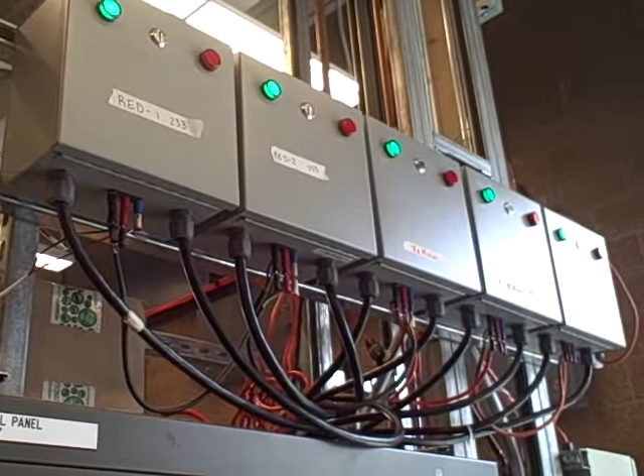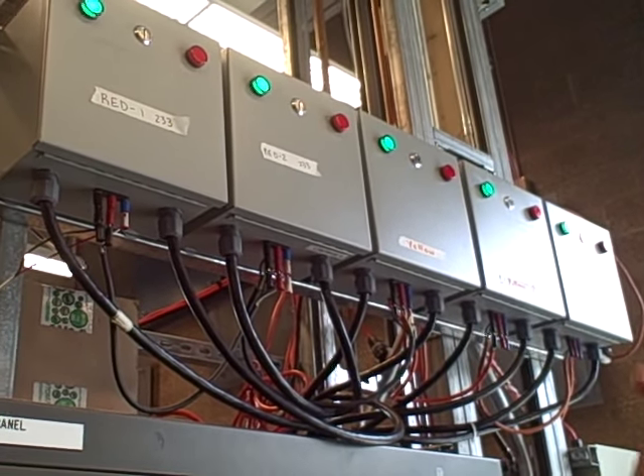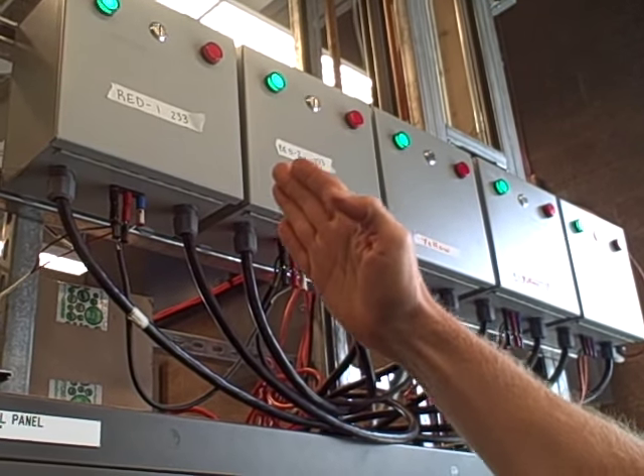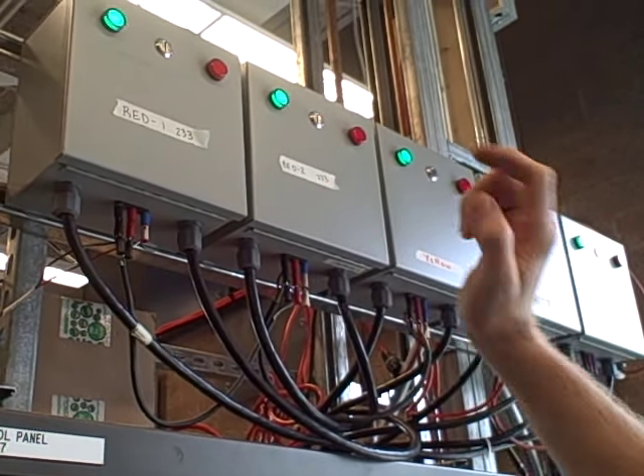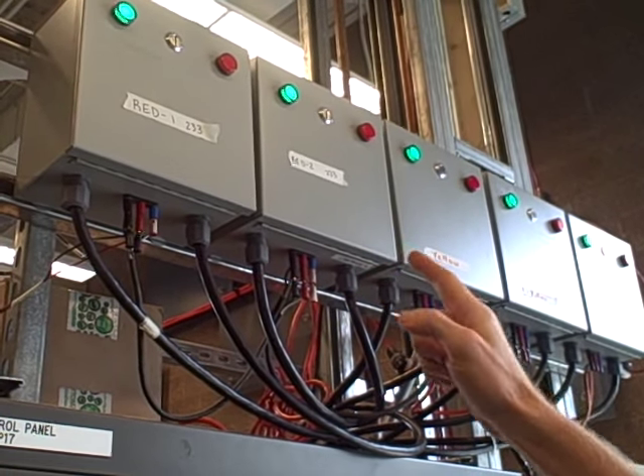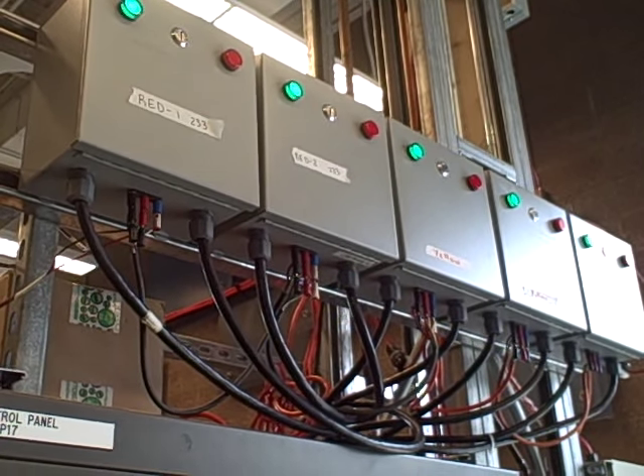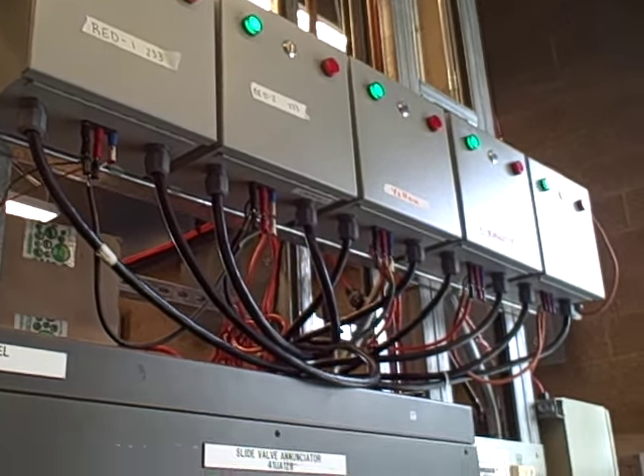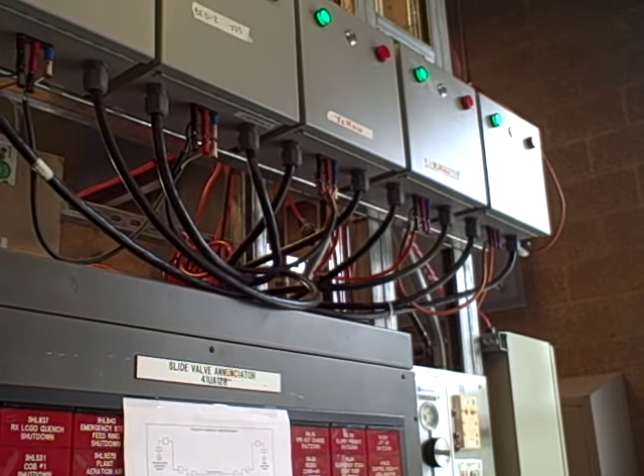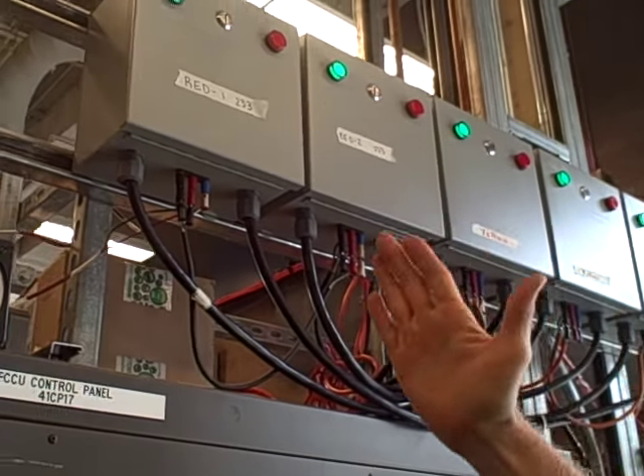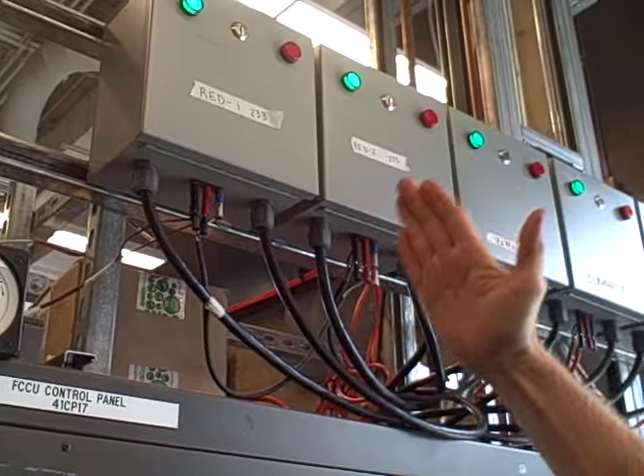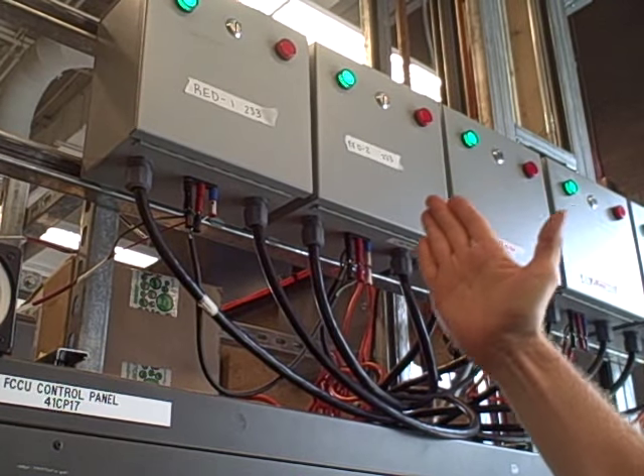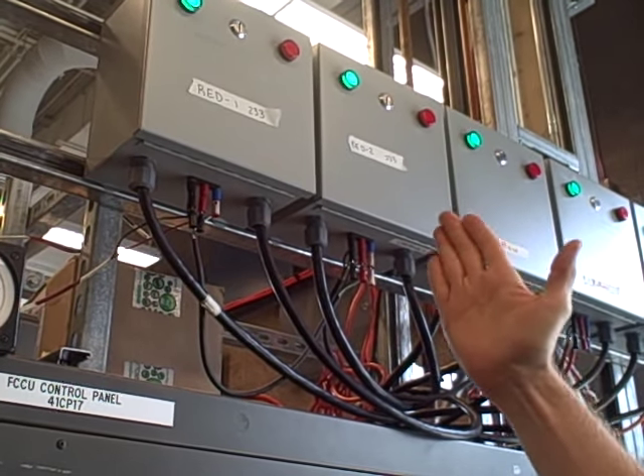Each breaker has a green light and a red light on the front. In keeping with the standard color convention for substations, green is off or tripped, red is on, it means danger. It may sound kind of backwards, we often think of green as being go and red as being stop. But in the power industry, green means off, safe, open. Red means on, energized, closed.